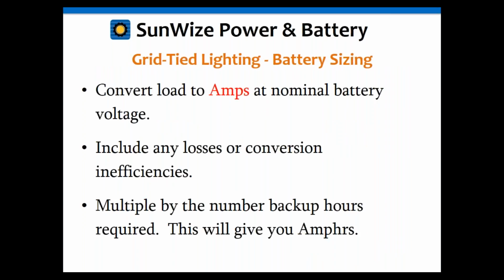Okay, so for sizing the grid tie for UPS type application, and again, this will be the same for the standalone solar. You're going to do it the same way because you're dealing with batteries. So whenever you're dealing with batteries, you're always working at amps and amp hours. So you're going to convert your load to amps. Okay, and that's going to be at the nominal battery voltage. If you have an inverter in there, you need to go through the process of including those inefficiencies and those equations and stuff like that. So you want to take that into account. Okay, and then you want to multiply that by the number of hours of backup time, and this will give you amp hours.